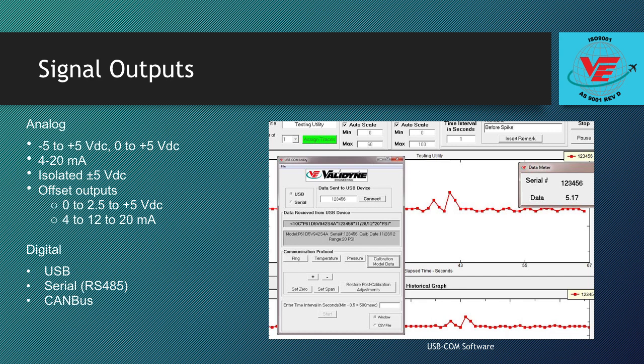The P55 is available with most commonly specified output signals. The standard output is 0 to 5 volts DC over the full-scale pressure range. The offset voltage options and voltage outputs isolated from the power supply are also available. The P55 can be ordered with 4 to 20 milliamp outputs and an offset of 4 to 12 to 20 milliamp output. The P55 can be powered by any unregulated DC power supply that puts out plus 9 to plus 55 volts DC at 20 milliamps or more.